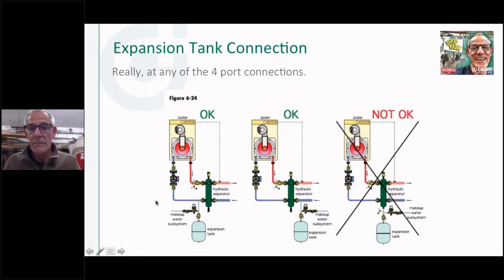Thanks, Ken. And so the problem over here is not the expansion tank location per se, but think about the dirt and any particles that come out of separation here, and they're going to come down and sit right on the diaphragm in the tank. As that diaphragm moves, as the water heats and expands, now I've got the rust and the crap that's coming out of my system abrading on that diaphragm. So all I'd want to do here is maybe put a T there and put an elbow and put a nipple and put my expansion tank so it's not directly below where my dirt removal function comes off the bottom of that separator. That's why the X is through there. Hydraulically speaking, it's a great spot, but I don't want my particles laying inside my expansion tank.